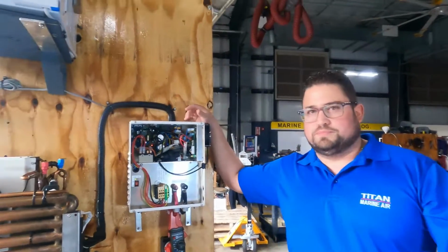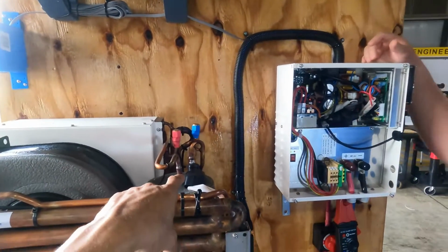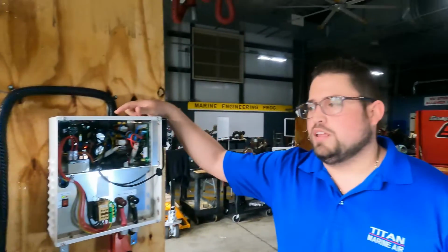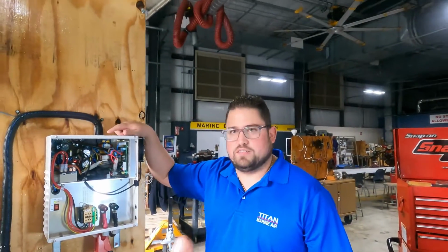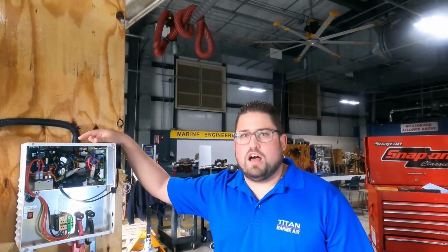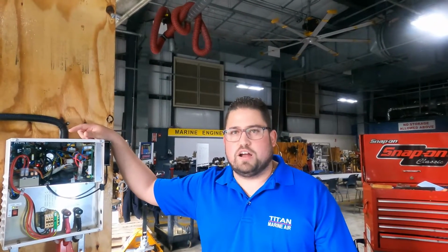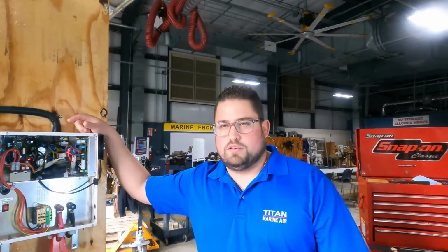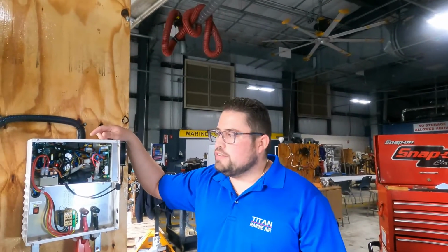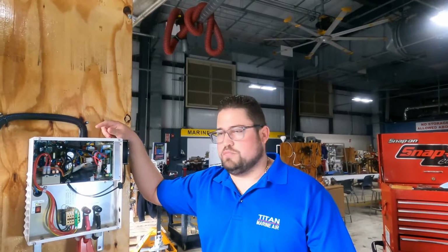Oh wow, but I have a question. The compressor itself is three-phase AC, no? Three-phase AC. Okay. Which allows you to vary the frequency on the compressor, which in turn changes the RPM on the compressor motor. With a frequency driver. Exactly. All of these compressors are brushless systems, three-phase brushless motors.